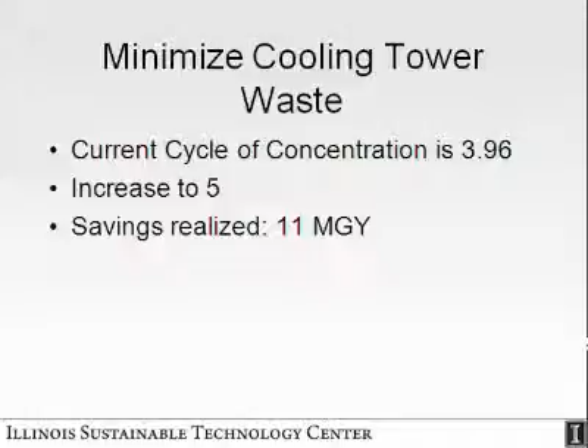If you run your reverse osmosis system more efficiently, you can save another 5 million gallons per year if you just go up to 75% recovery, or you can save 17 million gallons per year if you operate at 85% recovery. If you minimize the blowdown, going to a cycle of concentration of 5, you can save 11 million gallons per year. If you operate it even more efficiently, which is possible at this plant, you can save about 18 million gallons per year.